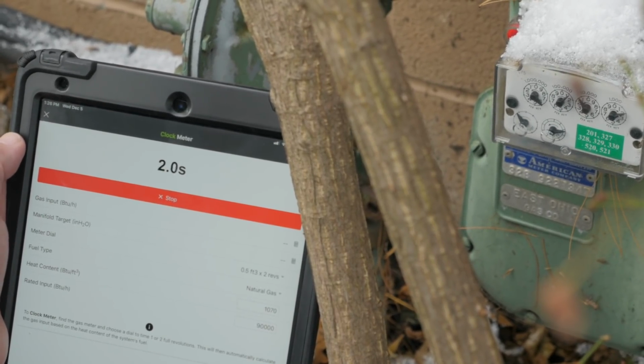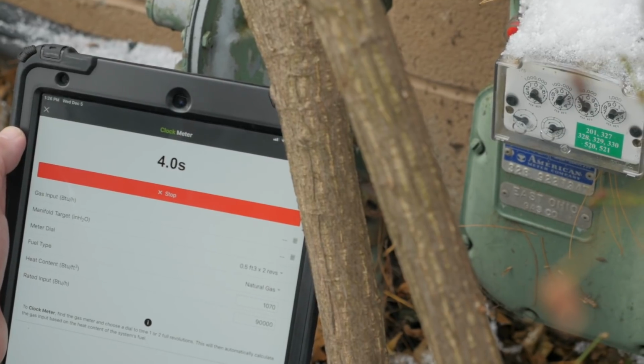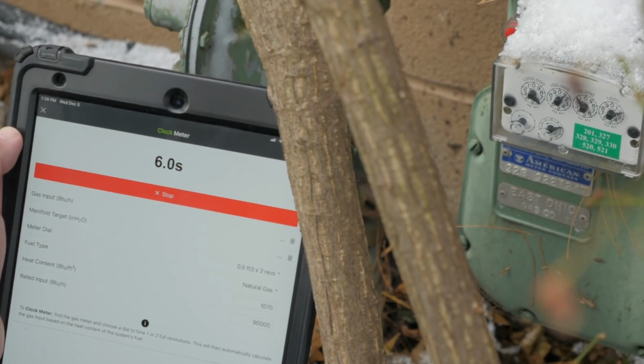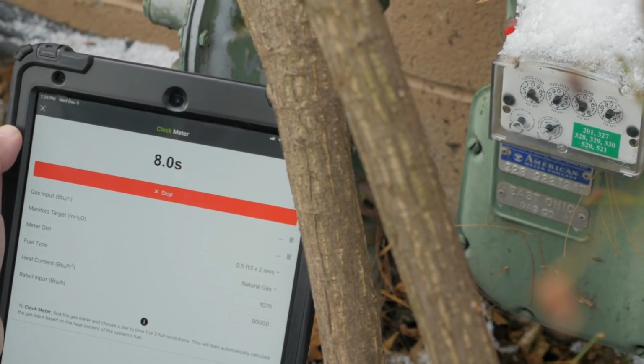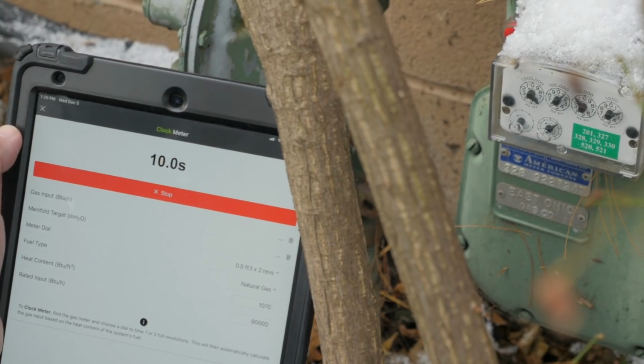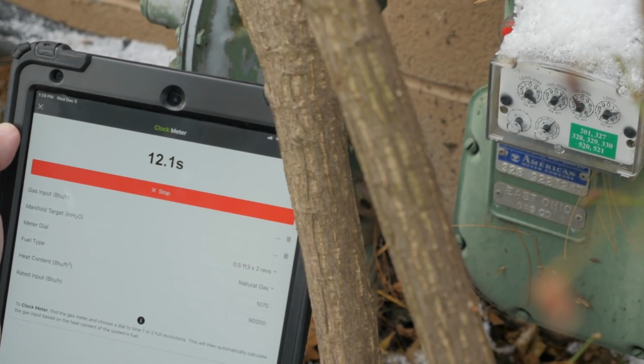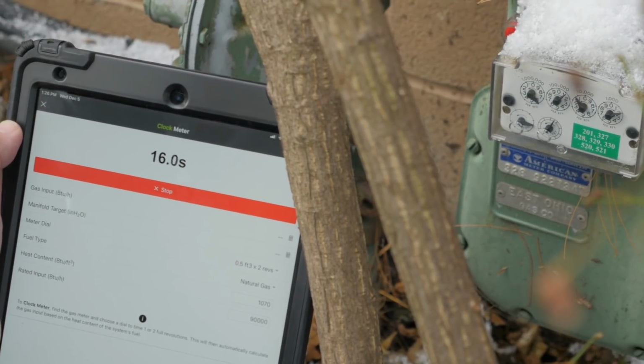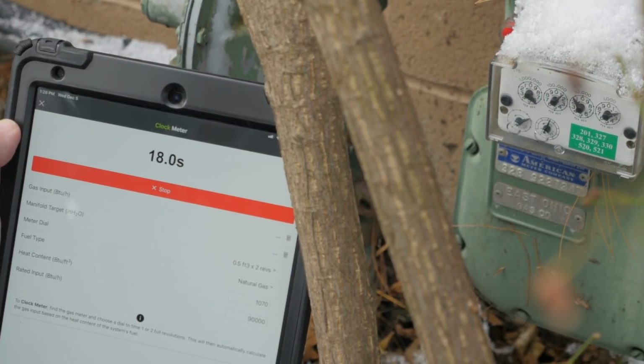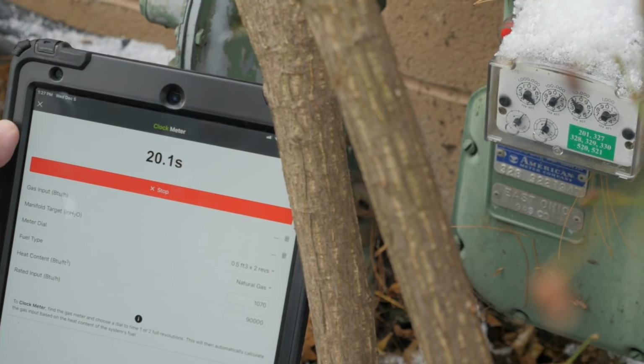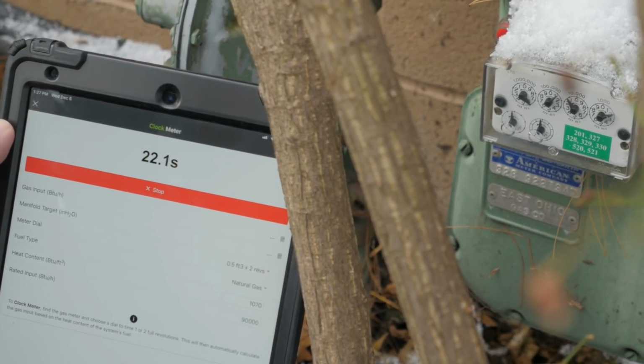So we get a question every once in a while: are gas meters really accurate? And yeah, they have to be. They're utility grade meters. You're billed on them, so they have to be very accurate. Now what you've got to realize is the heat content of gas varies, and that's why we set it up for an average heat content of the fuel, in this case 1070 BTUs for Ohio, because the heat content does go up and down a little bit.